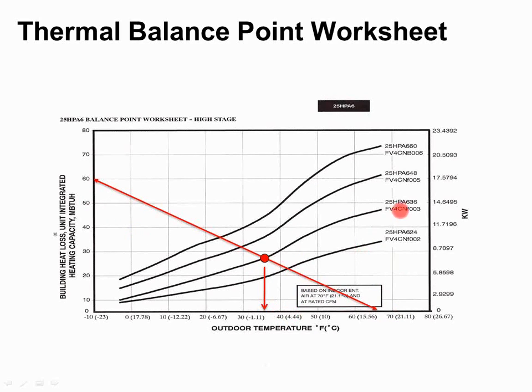If my cooling load is 3 tons, I pick this 3-ton one. I come down the line and see, okay, you know what? At 36 degrees outside, if I put this 3-ton unit in, I'm not going to be able to get enough capacity after that, right? So that means down over here, if I can even get it, this wedge is where I need to add some additional heat. Hopefully you guys can see me drawn with the little blue marker on here, right?